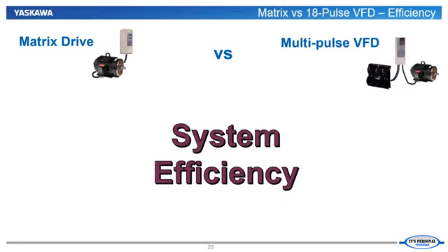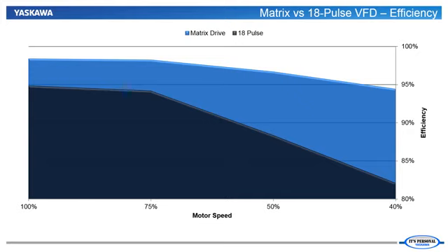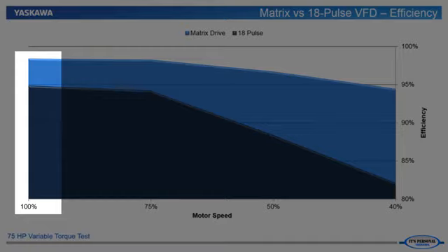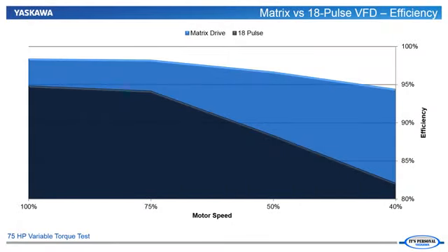Our next comparison will be to compare the operational efficiency of a Yaskawa matrix drive versus a VFD with a multi-pulse front end. Here's an example of two 75 horsepower configurations, one an 18-pulse and the other the matrix drive. Both are operating on a variable torque load. You can see they both perform well at rated load. Still, the matrix drive is at least 3% more efficient at rated power.